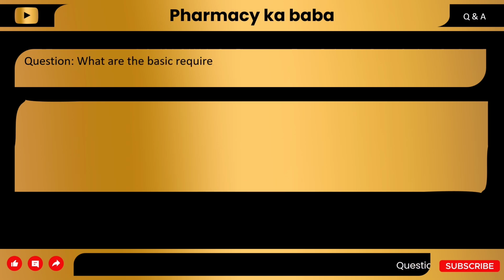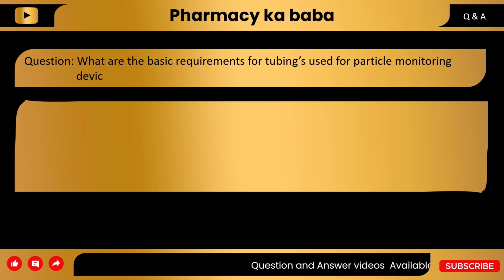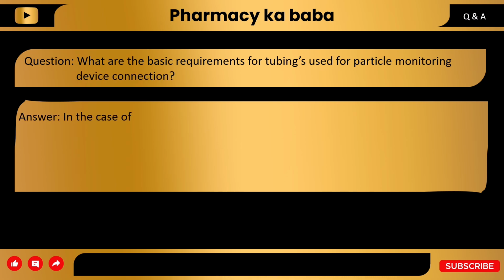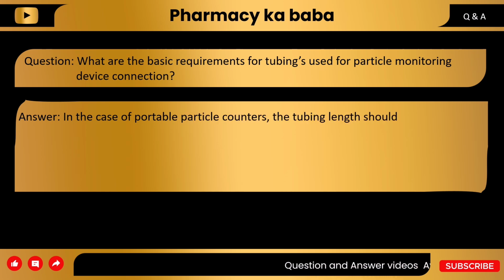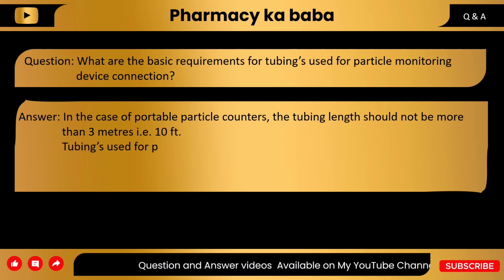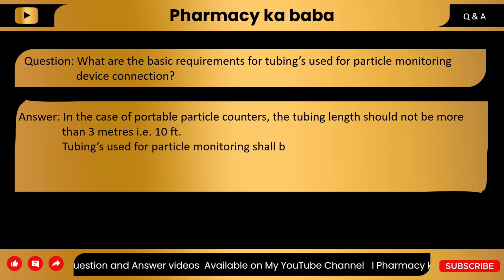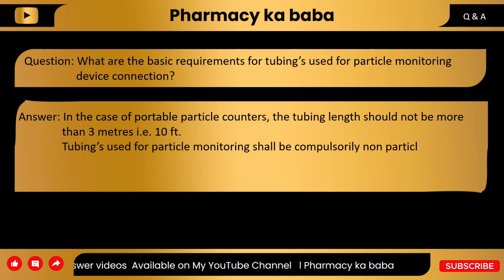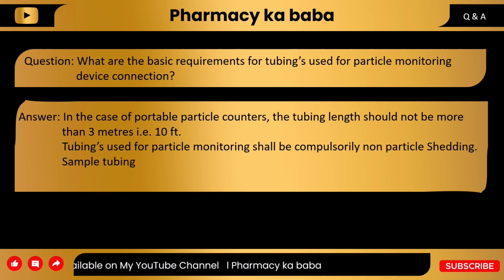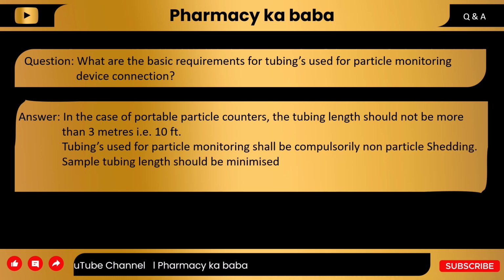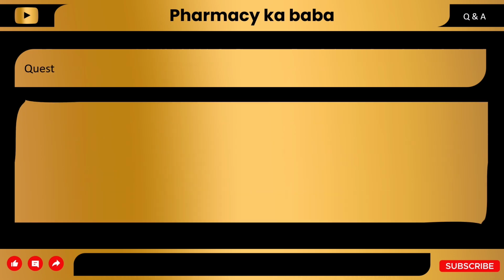Question. What is the basic requirement for tubing used for particle monitoring device connection? Answer. In the case of a portable particle counter, the tube length should be not more than 3 meters, that is 10 feet. Tubing used for particle monitoring shall be non-particle shedding. Sample tube length should be minimized, although tubing cannot be totally eliminated.